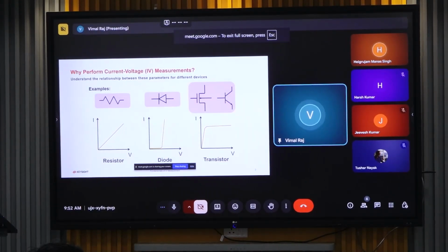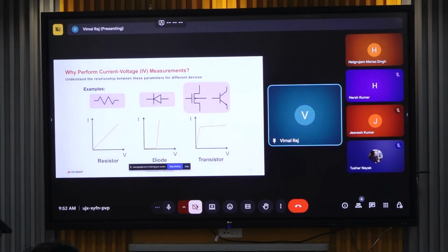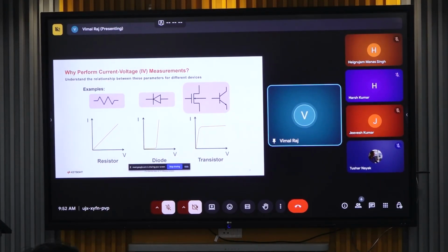Okay. Normally you want to see a characteristic showing the linearity of voltage versus the corresponding current. Like that, we set the voltage and measure the current. It will happen on all types of instruments. We are sourcing the voltage.